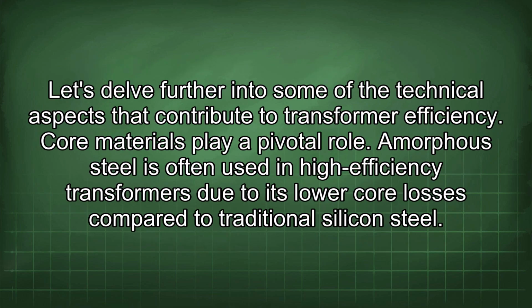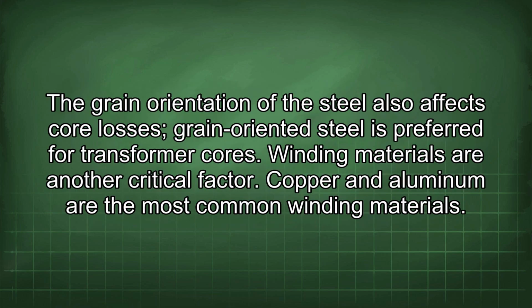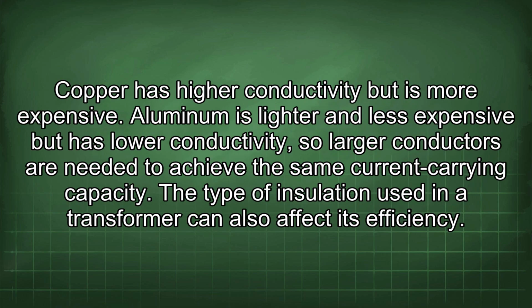in your area. Let's delve further into some of the technical aspects that contribute to transformer efficiency. Core materials play a pivotal role. Amorphous steel is often used in high-efficiency transformers due to its low core losses compared to traditional silicon steel. The grain orientation of the steel also affects core losses. Grain-oriented steel is preferred for transformer cores. Winding materials are another critical factor. Copper and aluminum are the most common winding materials. Copper has higher conductivity but is more expensive.